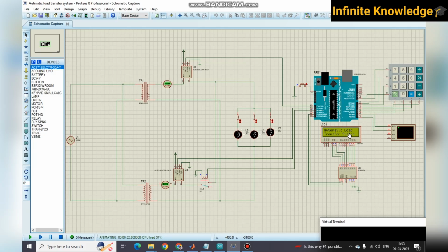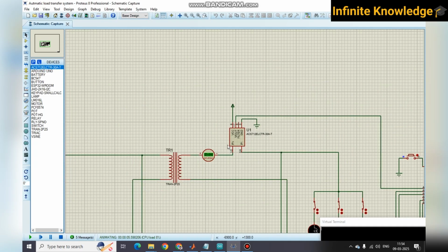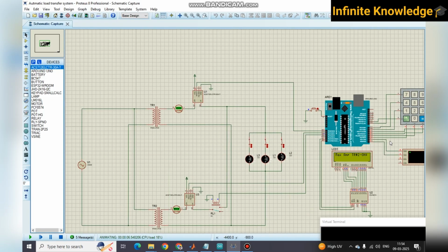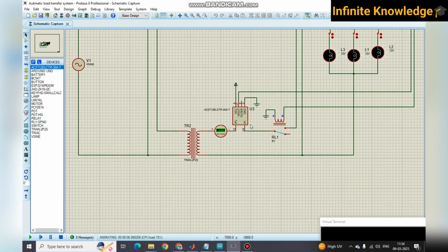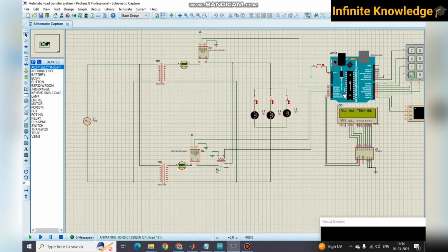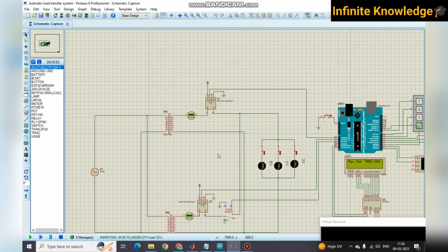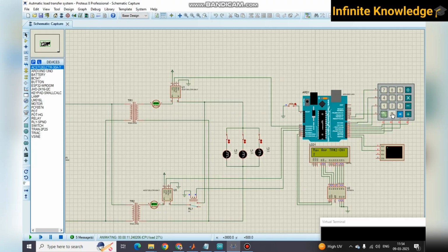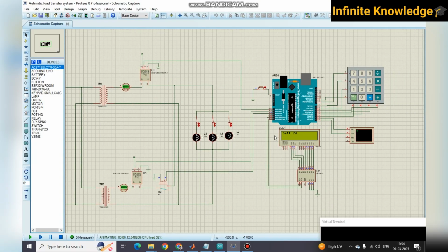What I need to do is set the maximum ampere at which the TR2 breaker will turn on. This one is a breaker, so I need to set a current limit. At which ampere does this breaker turn on? This is the main current sensor, which senses the 23 ampere and feeds it to the Arduino, and this is the secondary sensor, which is connected with TR2 and is also connected to the Arduino. So at the maximum ampere on which TR2 turns on, it senses this ampere. If it is more than 20, then I need to turn it on. So I add 20, because above 20 I need to turn on this breaker. Okay, I set 20.